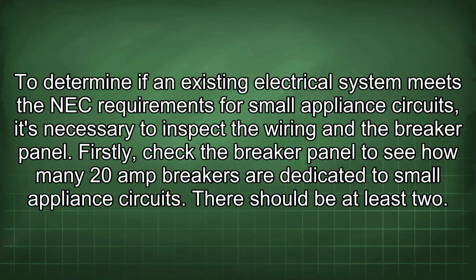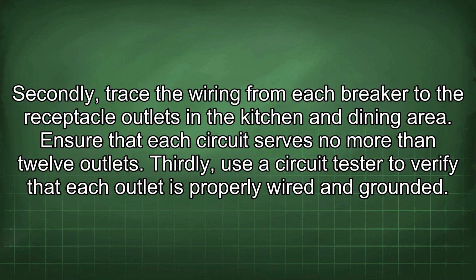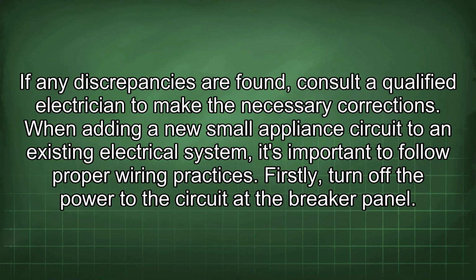To determine if an existing electrical system meets the NEC requirements for small appliance circuits, it's necessary to inspect the wiring and the breaker panel. Firstly, check the breaker panel to see how many 20-amp breakers are dedicated to small appliance circuits. There should be at least 2. Secondly, trace the wiring from each breaker to the receptacle outlets in the kitchen and dining area. Ensure that each circuit serves no more than 12 outlets. Thirdly, use a circuit tester to verify that each outlet is properly wired and grounded. If any discrepancies are found, consult a qualified electrician to make the necessary corrections.